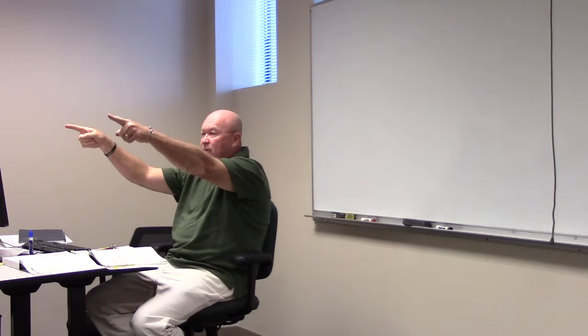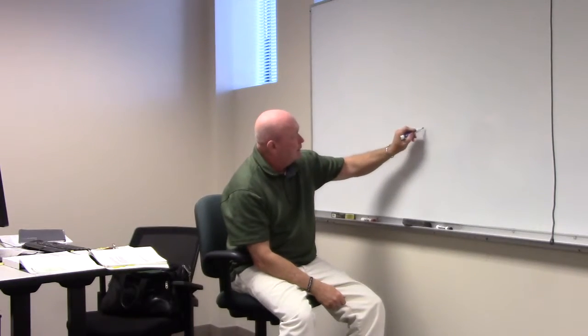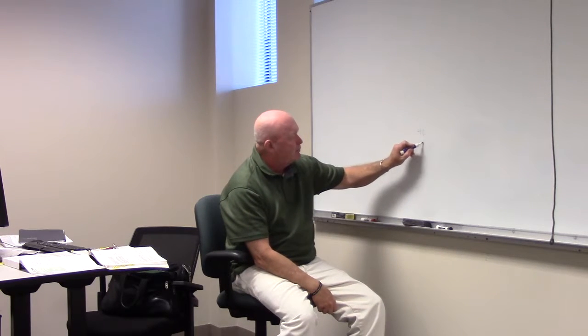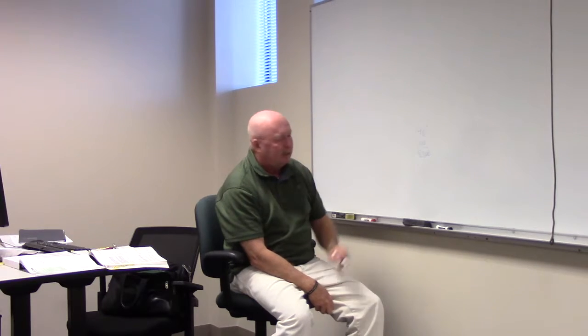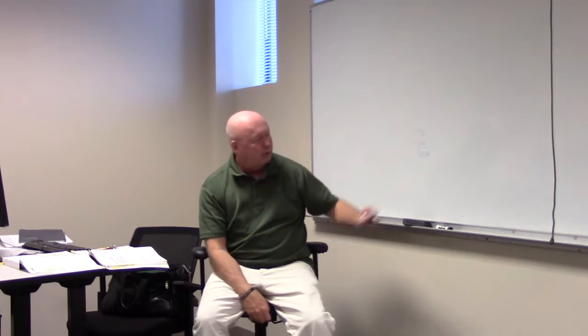Okay. The other thing we learned is that show windows are by the linear foot. In other words, they're 200 volt-amps per linear foot for a show window. Are you going to have that in a retail store, a show window? Yes, sir. So we had a 40-foot storefront, and it says 200 volt-amps per foot, doesn't it? So we're going to multiply 40 times 200, and we're going to get what? 8,000. So we'd have 8,000 volt-amps just for show window lighting in a store.